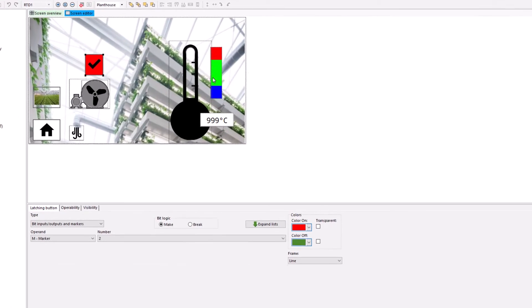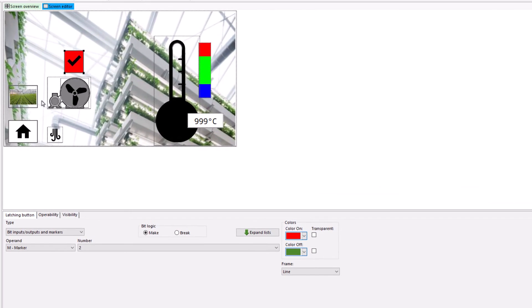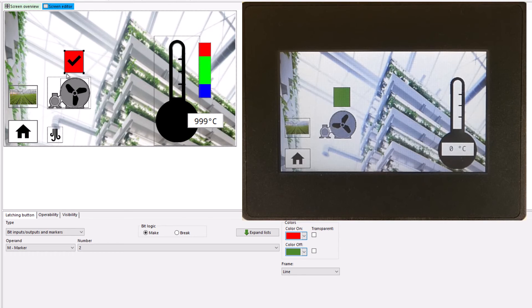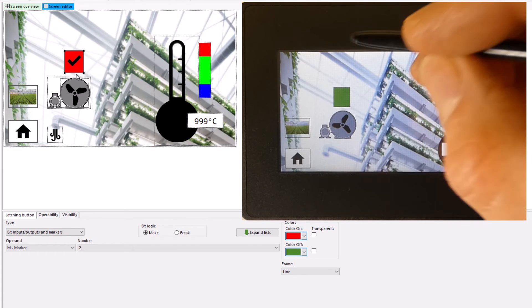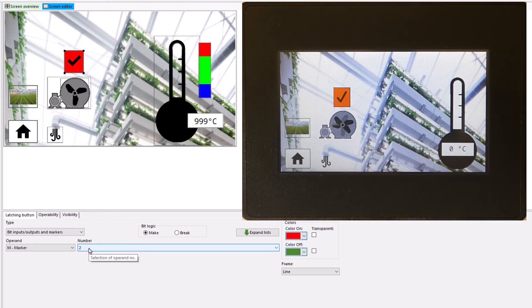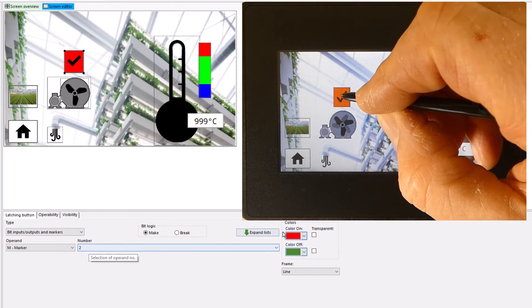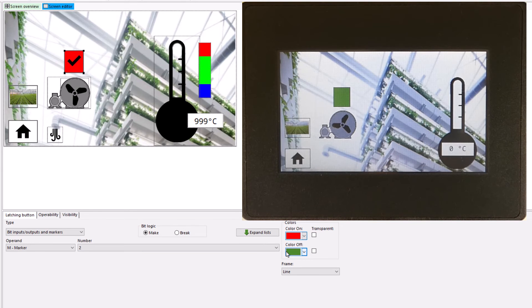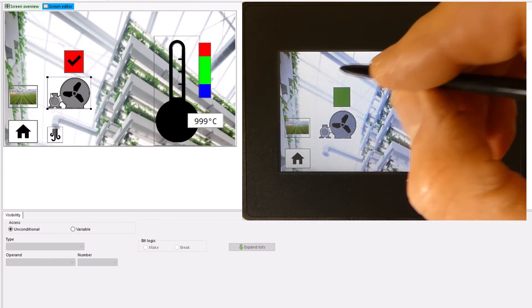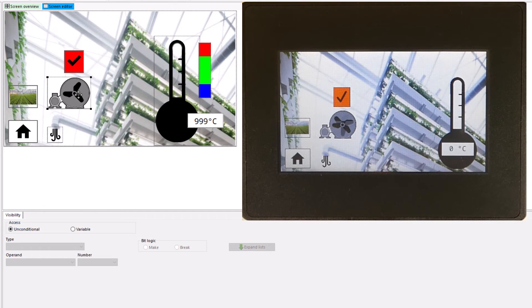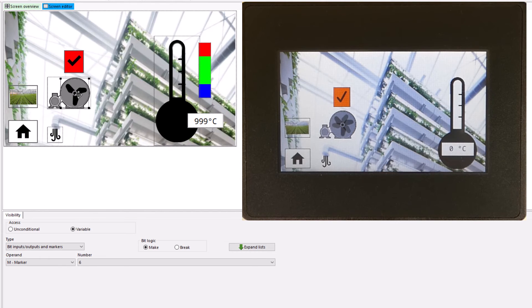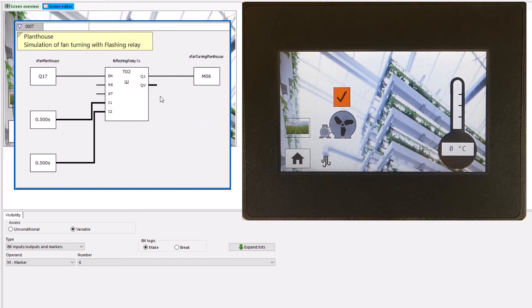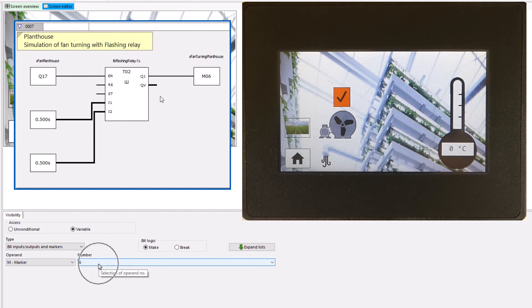The universal buttons for switching screens are again located on the left-hand side of the last screen. In this case, the example fan for temperature control is switched on and off using a latching button via marker 2. The color changes for the status change were defined as red and green. The symbolic fan is represented by two overlapping bitmaps. The second bitmap for the simulation of the rotating fan only contains the fan blade wheel, which is controlled at 1 Hz via marker 6 using a flashing relay.